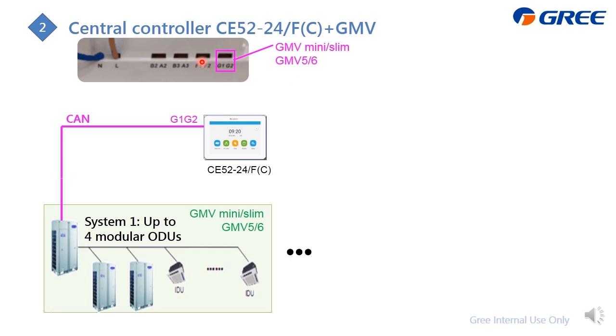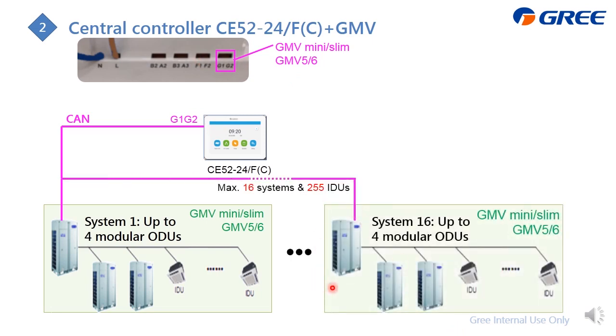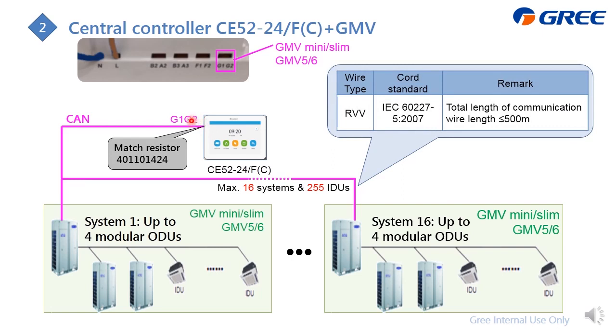And if it is for multi-system, you need to find out the master outdoor unit and combine the G1, G2 on every system's master outdoor unit together and connect here. And also don't forget the match resistor to ensure the communication. As for the wire, here are the requirements of it.